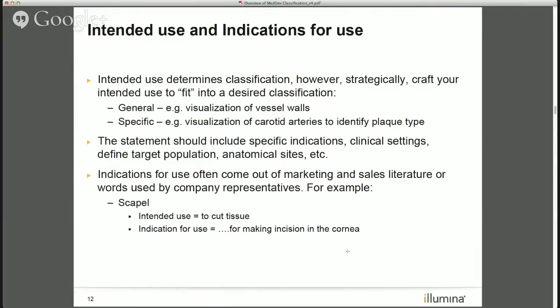You can craft your intended use language to fit, if you will, into a desired classification. If your initial intended use is somewhat general — just saying 'vessel,' for example — that's probably a lower-risk classification. If you become more specific, such as specifying carotid arteries, then depending on the clinical setting, that could be considered high risk because it's an artery and it's a carotid, potentially falling into a Class 3. The words you choose in your intended use can really drive that classification.